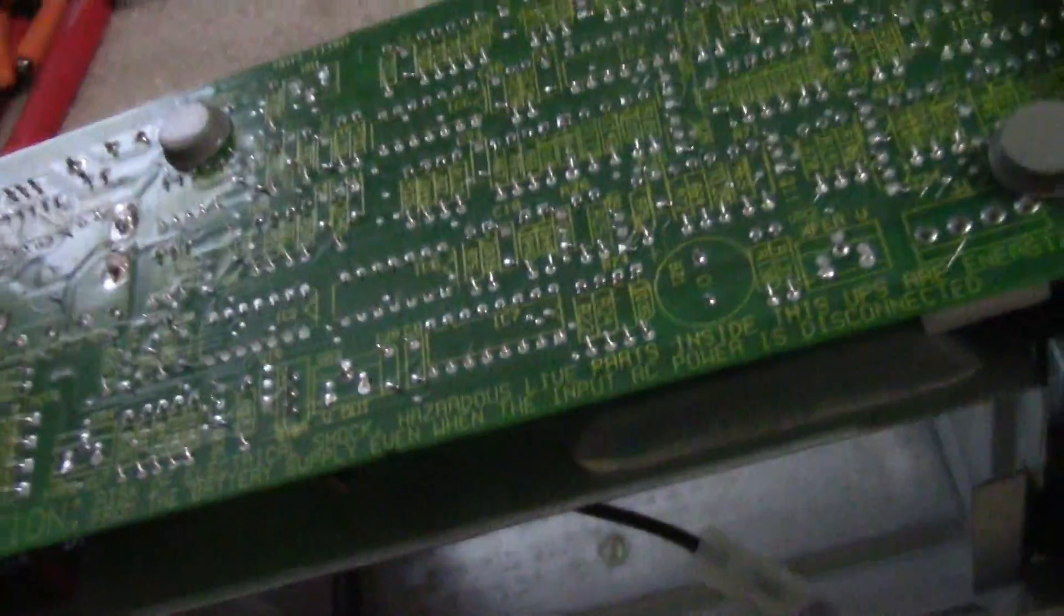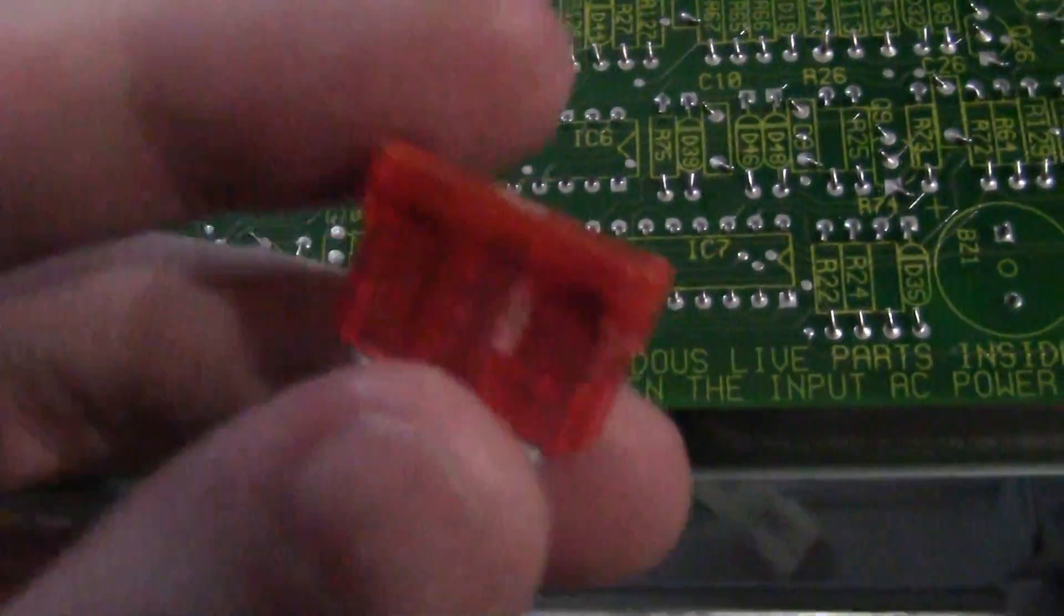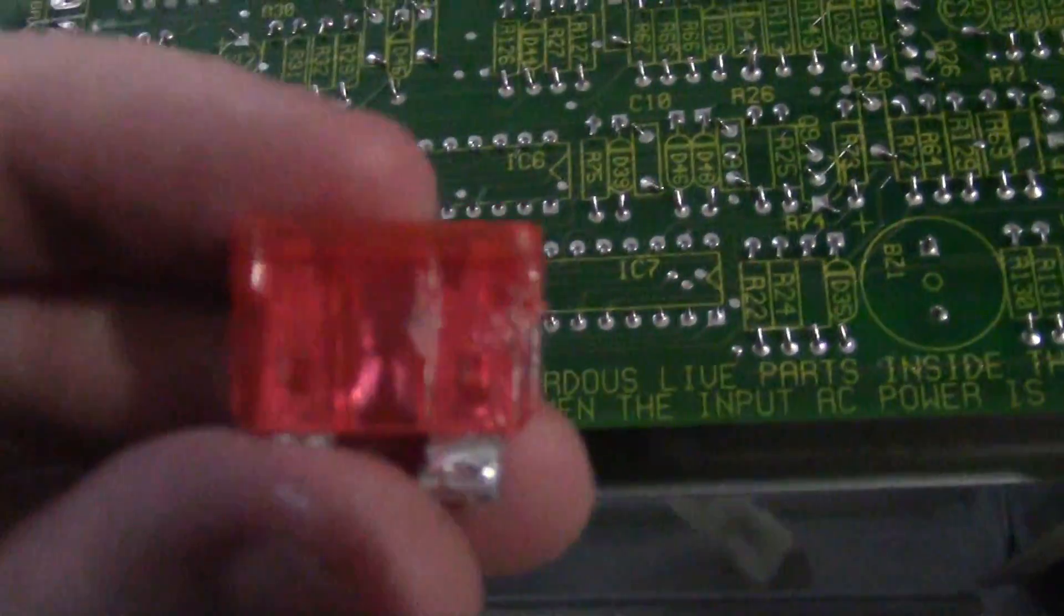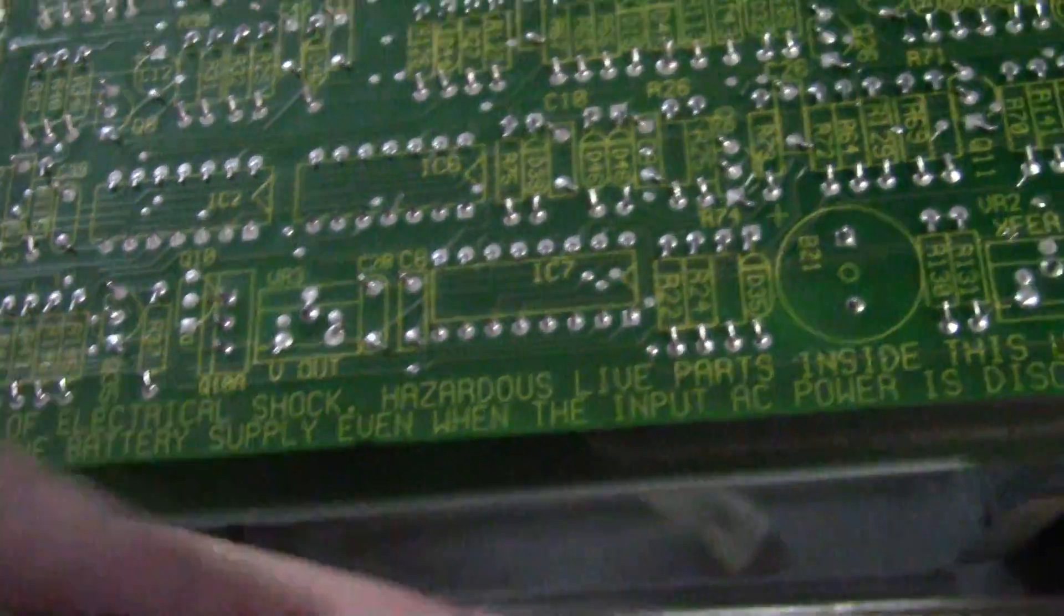So I took the panel off of this and looked at the circuit board, and I found fuse one which is right here. I can get the camera on it where those terminals are. Fuse one had this 40 amp fuse in it, and if you look it's open. I broke it getting it out but I got all the main pieces out.